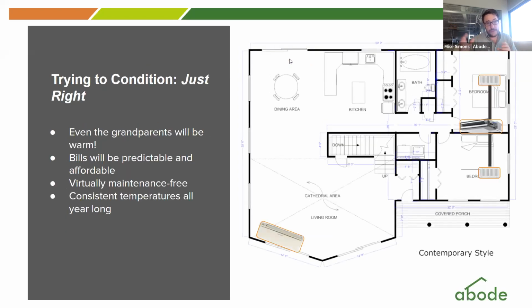Instead, what we would propose is something like this. It still needs 18,000 BTUs, but now they have, say, a 9,000 BTU ductless unit covering the main area, and then over on this side of the house, another 9,000 BTU ducted unit, and off of a medium static unit you could even add a separate emitter into the bathroom.